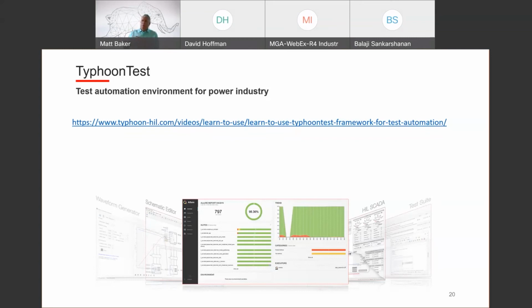You may have caught it that Typhoon is Python based. Python has an awesome test scripting capability called PyTest. Typhoon has built on that with an API that makes it easier for a non-Python user to use it. We've developed this Typhoon test approach where you can take that microgrid system in your C-HIL test stand and start it running the test, going through every permutation all night long. When you come in the next morning, it gives you this Allure test report. It tells you how many tests it ran, how many passed, how many were faults, how many were actual failures—it can do all of that for you. So a very, very important capability here.